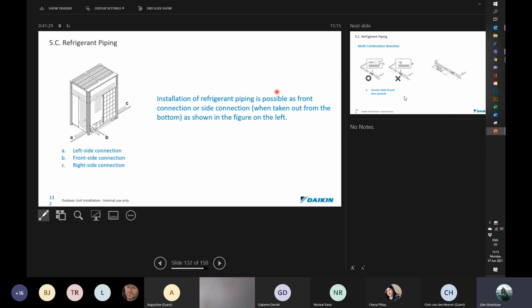When we get to looking at gas risers just now, look at the access points provided and recommended for condenser piping configurations. And you'll see that the 3 of them that are recommended are in through the front, okay, and either in left or right underneath the unit. Okay, a lot of guys are tempted to take the piping out the back of the unit, and we try and advise that you don't do that because you start adding extra lengths of piping onto it, which could cause a problem and create extra work for you.